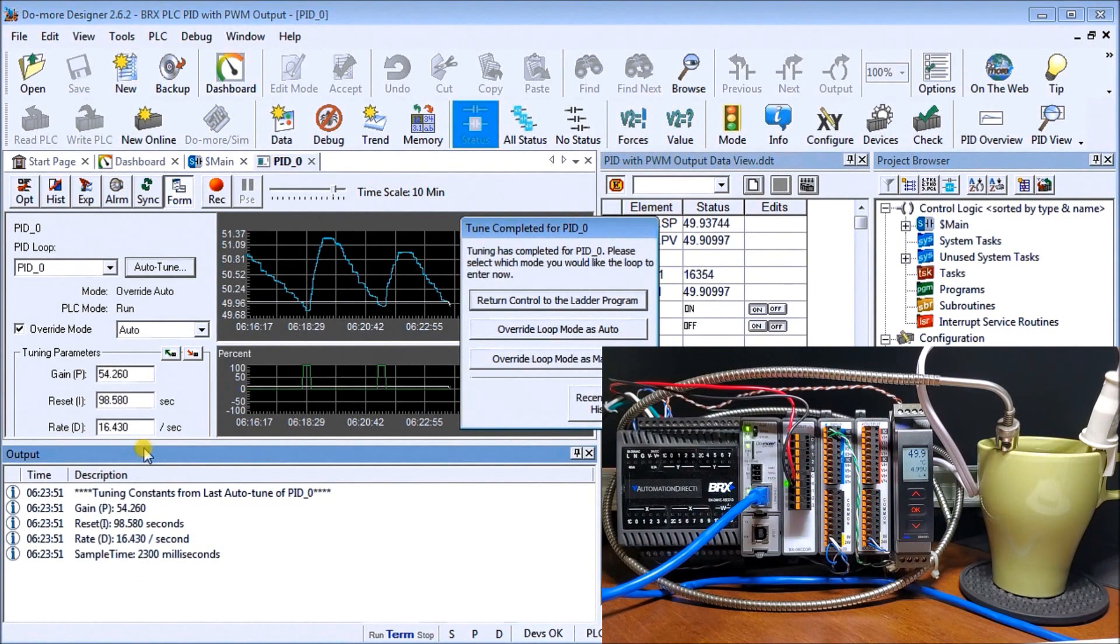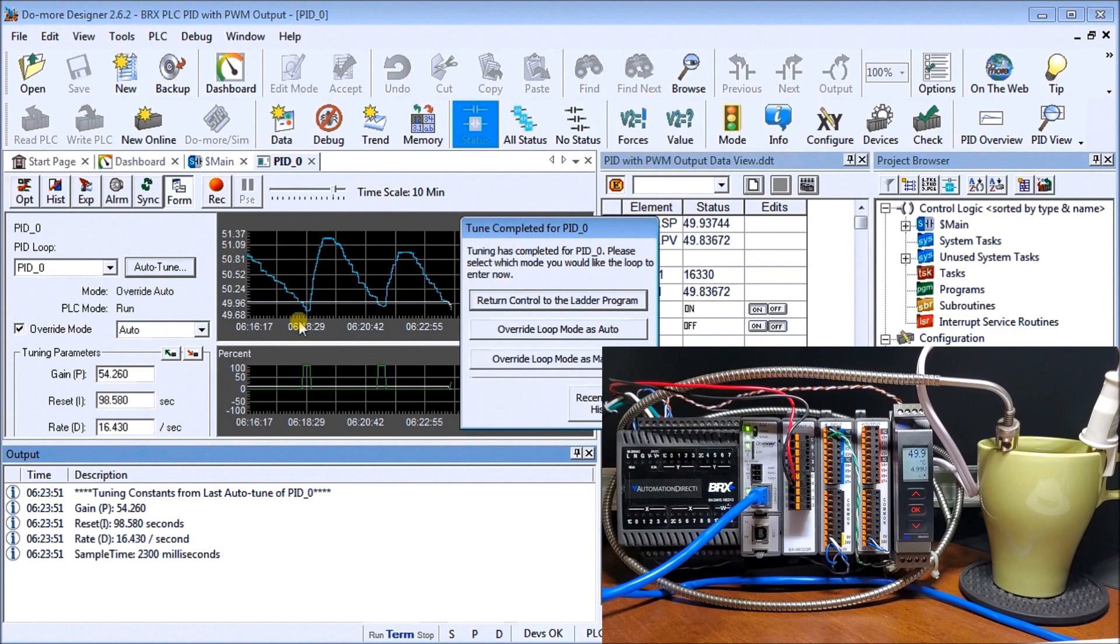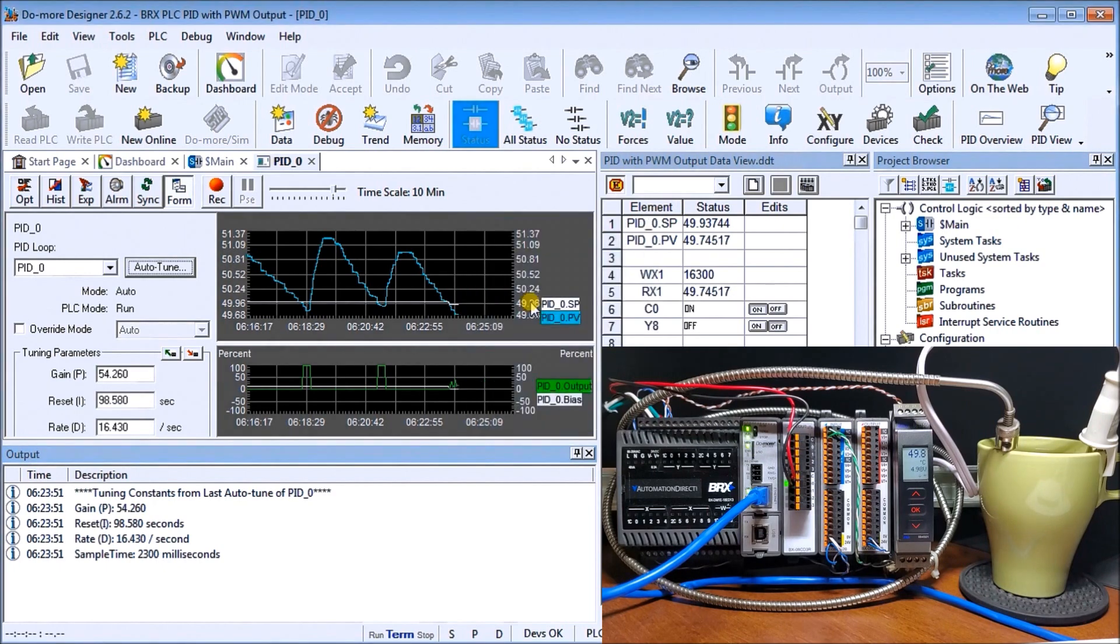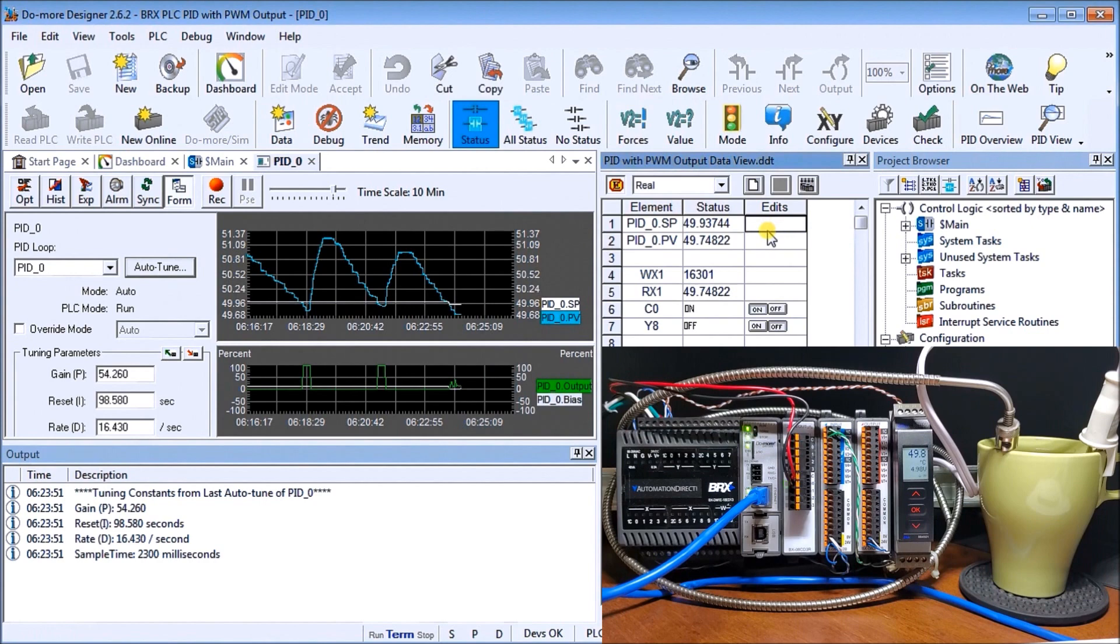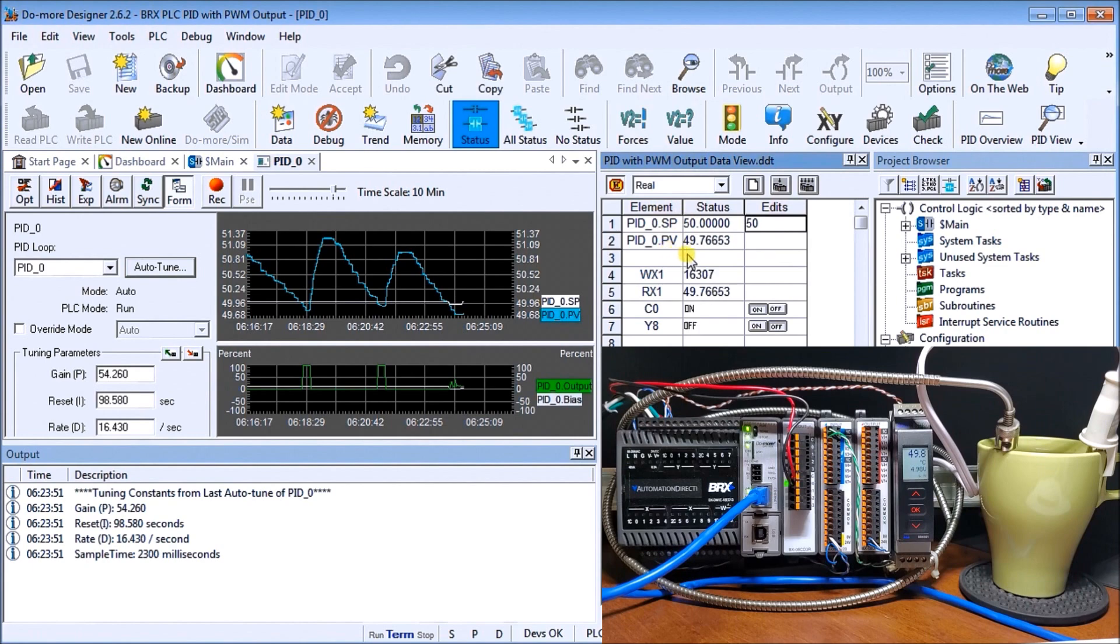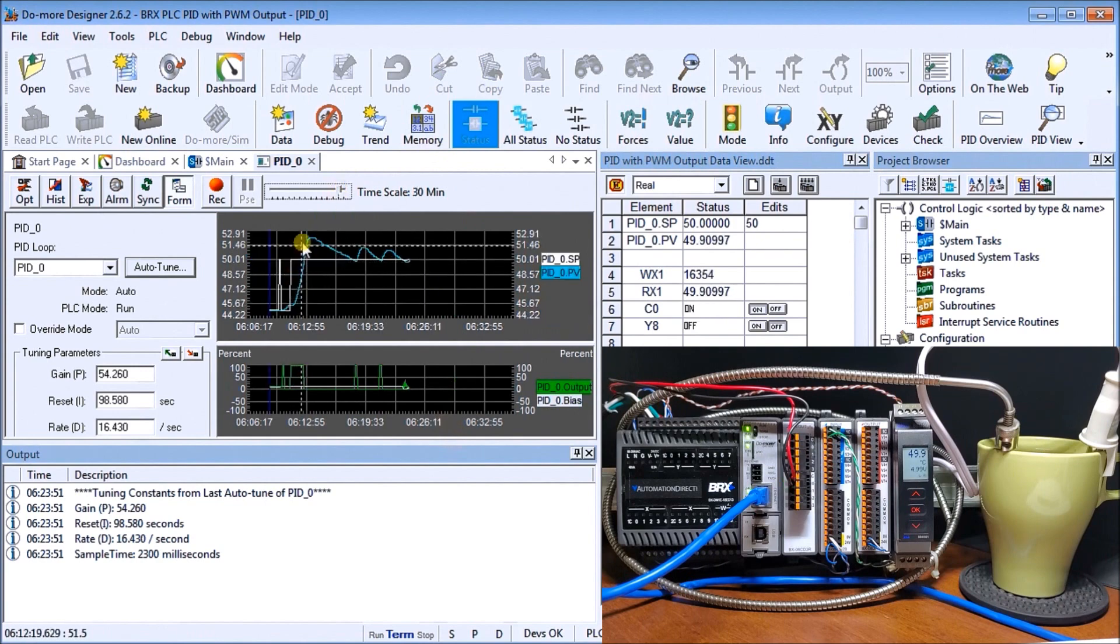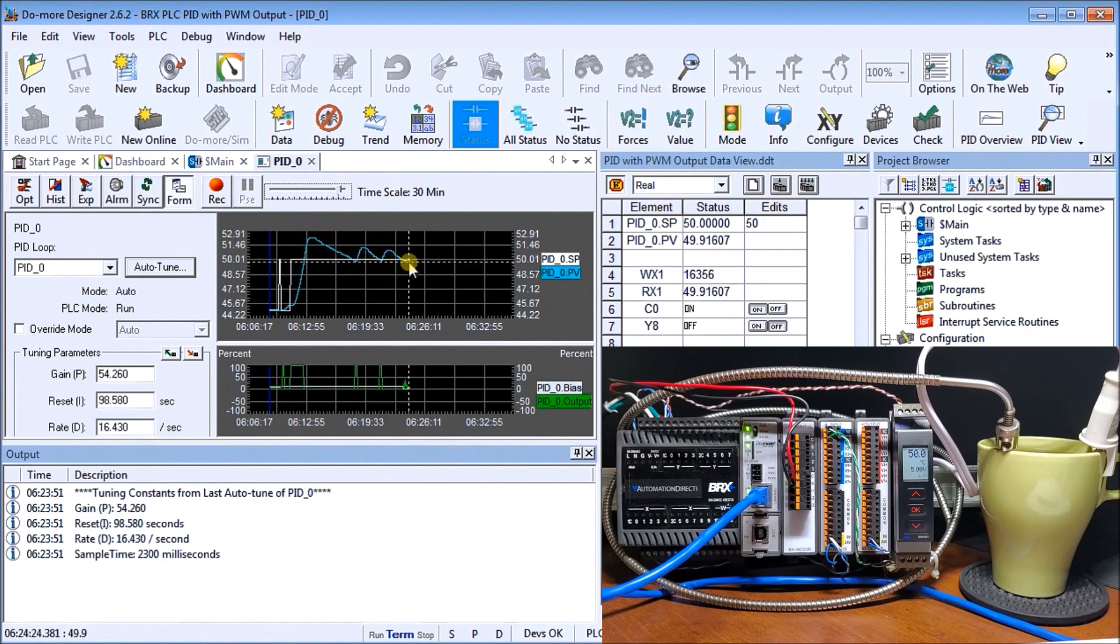We've completed our auto tuning and it's asking me to return control to the ladder program or overwrite the loop parameter or manual tuning. Let's return control to the ladder program. We have our set point at 49. Let's change that set point back to 50. If we look back, you can see our two exact loops as we go through here until it finally corrected and did our auto tune itself.